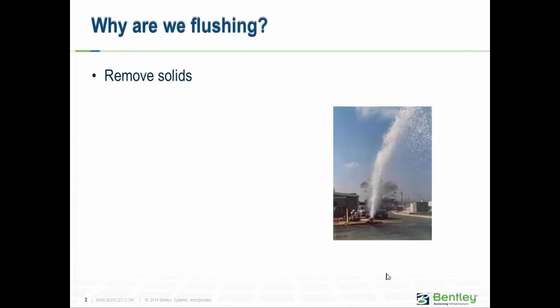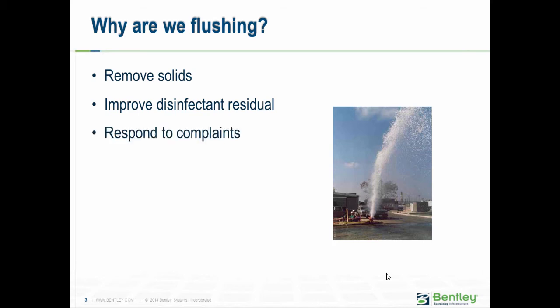Why are we flushing? Removing solids is usually the most common reason — you're trying to increase velocity. Improving disinfectant residual means moving clean water into an area with stale water. Responding to complaints is kind of hit or miss — it depends on what the exact complaint is. In some cases, the goal is removing biofilm, where you need to get a very high velocity in the distribution system. Each of these reasons requires a different approach.